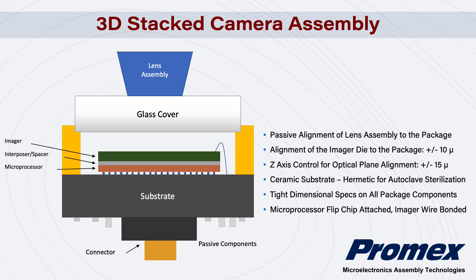And this is what the final 3D stacked camera assembly for the endoscope looked like. There's a lens on top of the cover glass and an image sensor, which along with the lens creates a miniature video camera. The entire assembly is just 8 millimeters across, an assembly with incredibly close dimensional tolerances that's the size of the eraser on the end of a pencil, forming a high-definition stereoscopic camera in full color. The entire assembly is hermetically sealed and can withstand autoclave sterilization. A successful design has got to work, must be robust, and have good economics, and we are currently fabricating these units for the customer at our primary facility in Silicon Valley.